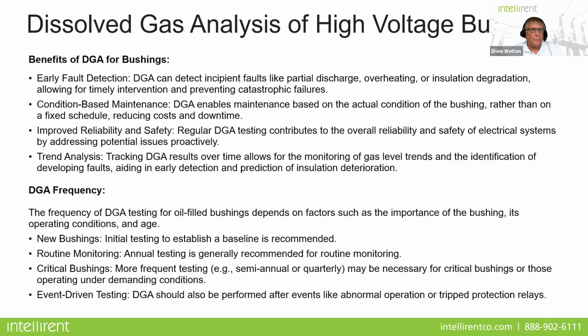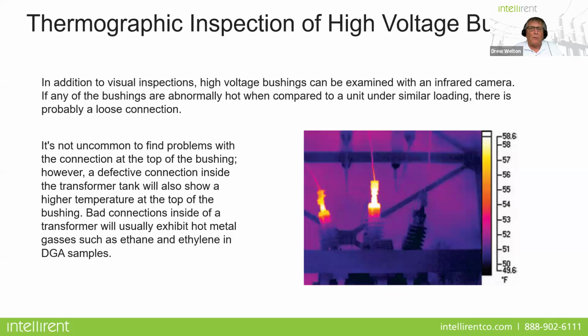do a DGA. Another very popular way to look at the health of bushings is through thermographic inspection. In addition to your visual inspections, your high voltage bushings can be examined with infrared cameras. If any of the bushings are abnormally hot compared to the unit under similar loading, there's probably a loose connection, like we talked about earlier. And the good news, of course, is that you want to do it while the transformer is online.